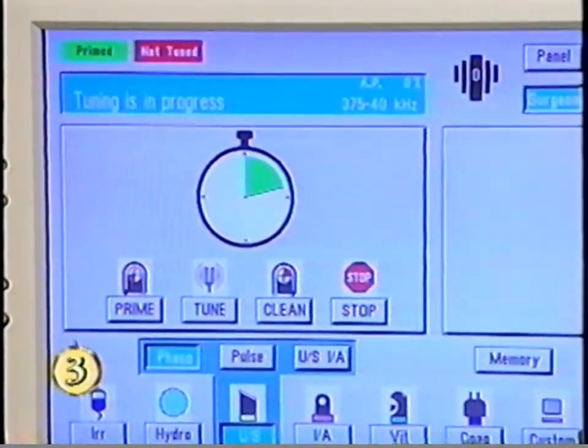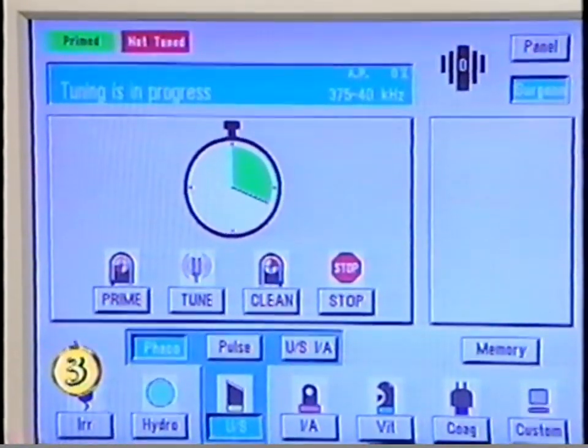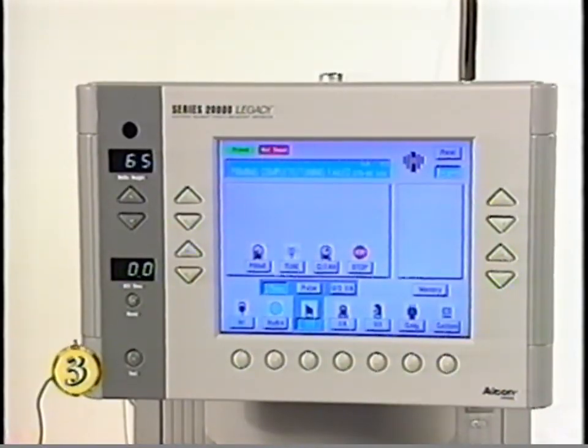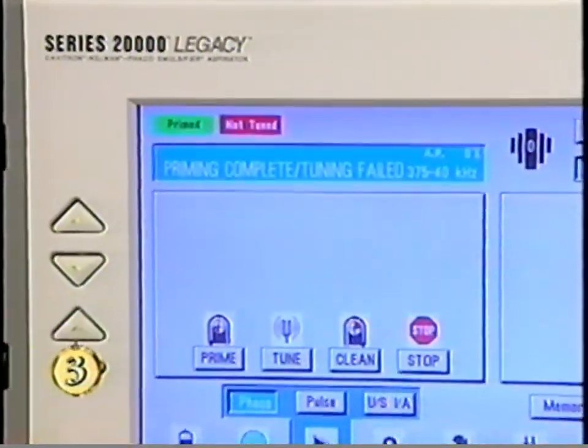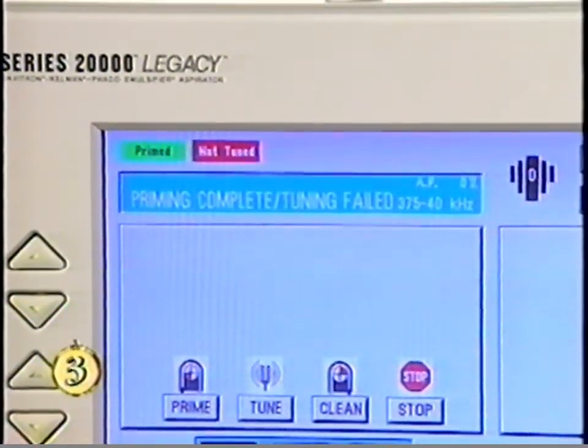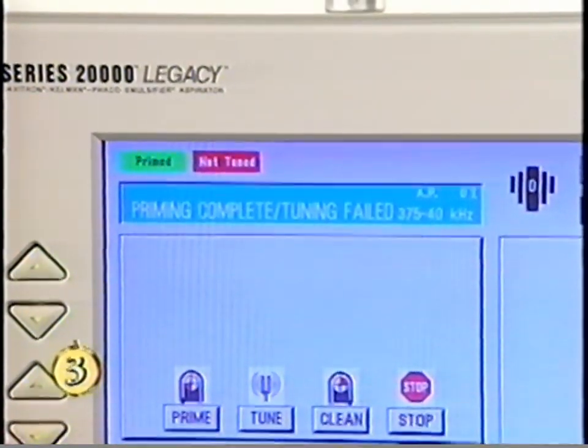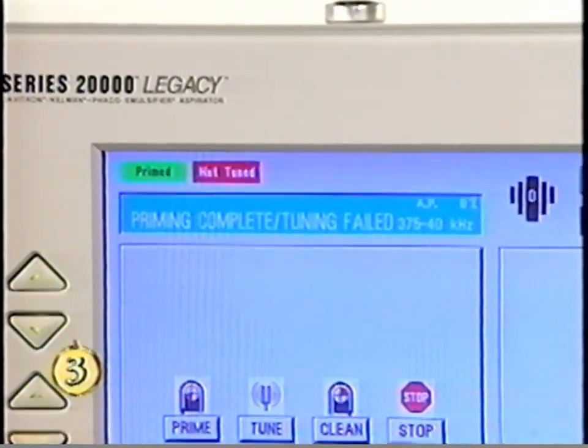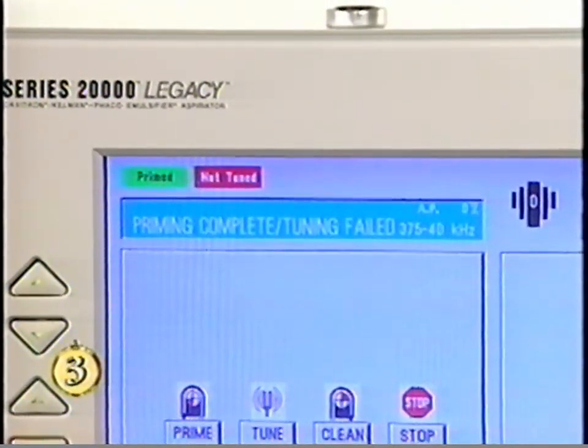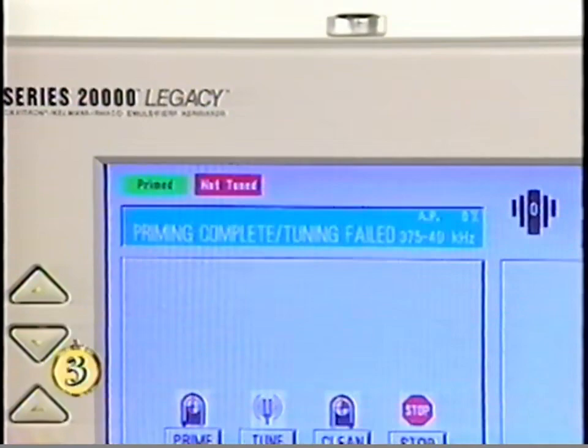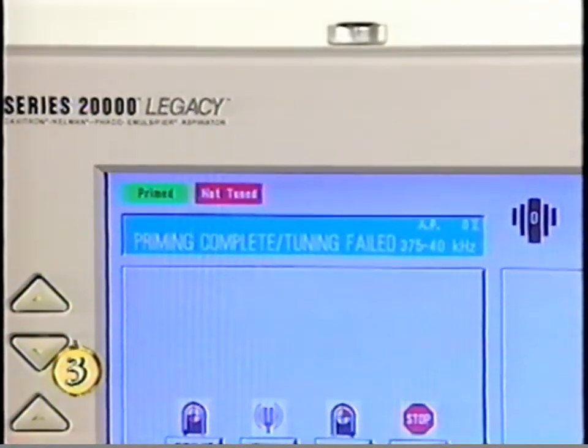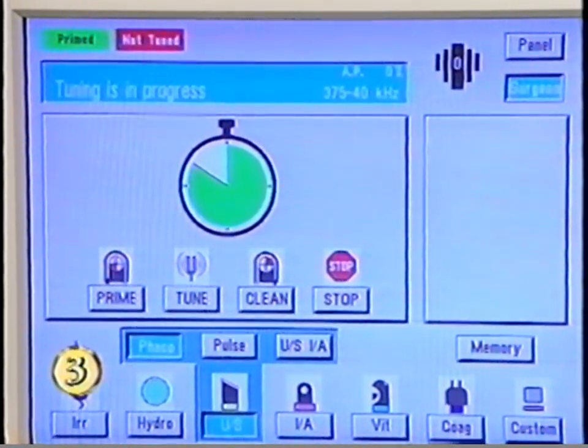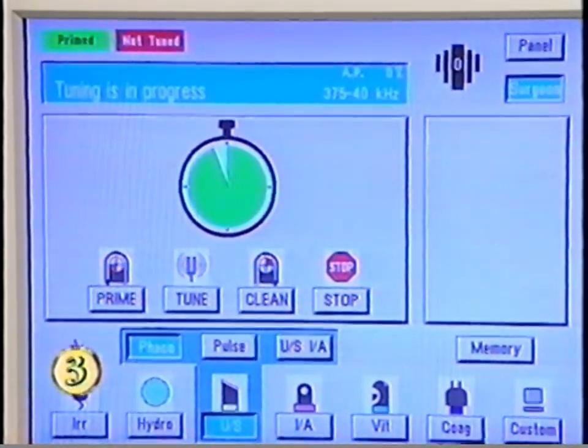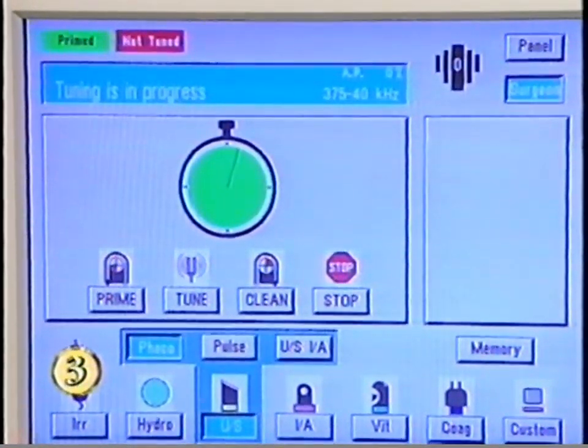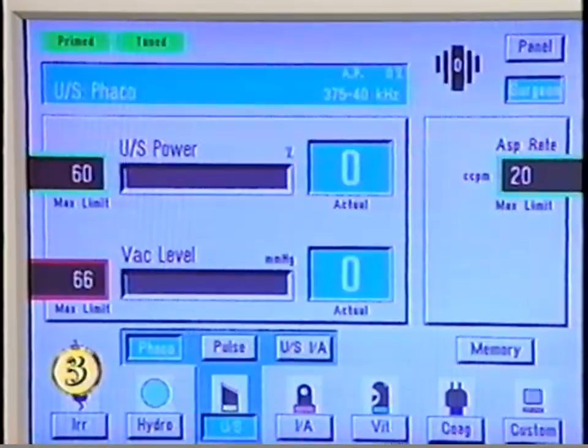After tuning has been successfully completed, the tune status indicator will turn green. If tuning fails on the first try, the unit will automatically attempt a second tuning. After tuning, a flow test will run in phaco and pulsed phaco modes to signal aspiration flow within the tip and handpiece. If the handpiece fails this flow test, check the troubleshooting section of the operator's manual for corrective action.